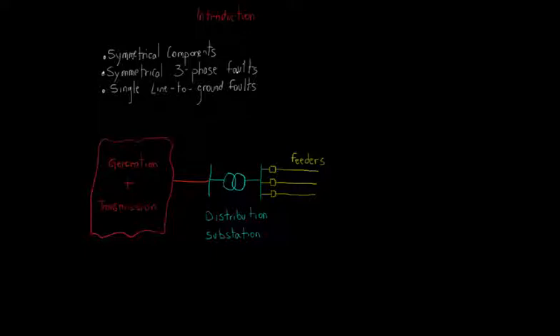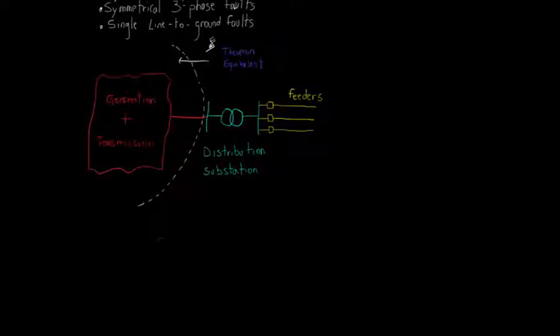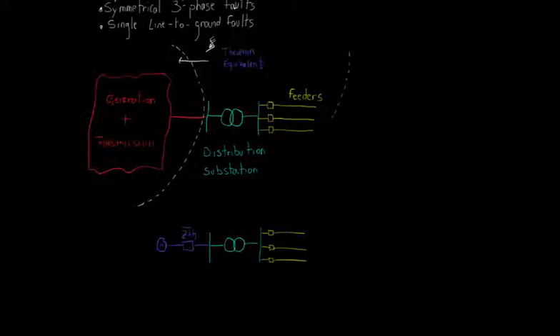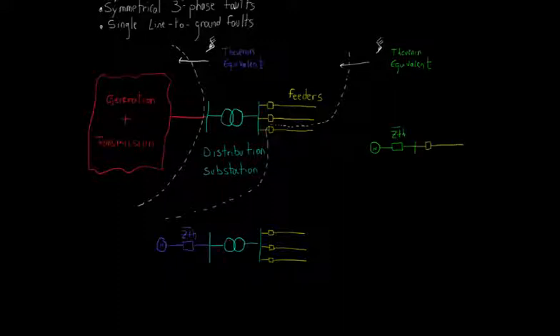As our goal is to study only the distribution system, we can consider the Thevenin equivalent seen from this point. Then, the red block is represented by a voltage source behind an impedance, usually called Thevenin equivalent impedance, which is exactly the vSource element in OpenDSS. Let's say, for example, that we wanted to study only one feeder of the distribution system. In this case, applying the same principle, we would end up with a simplified circuit with a different Thevenin equivalent impedance and a feeder in study.